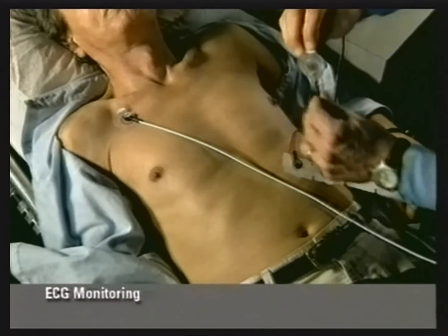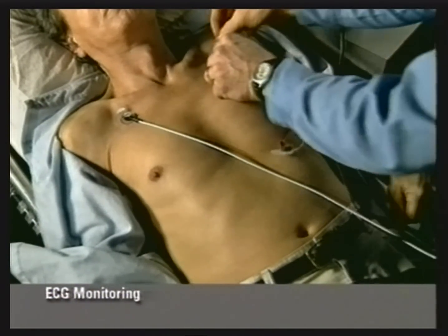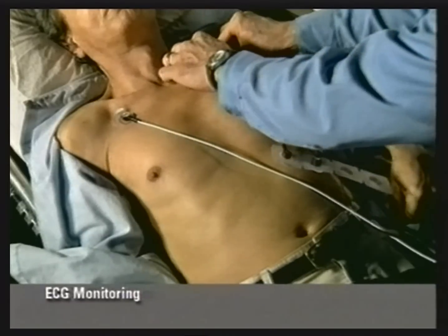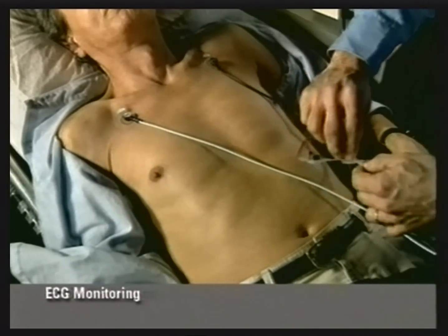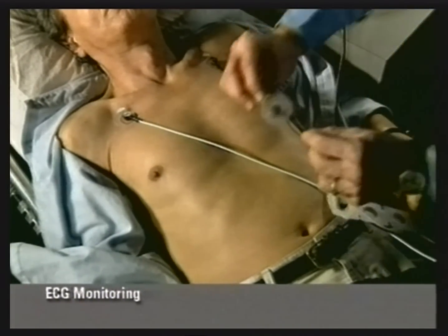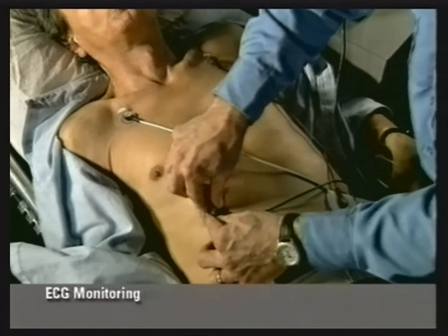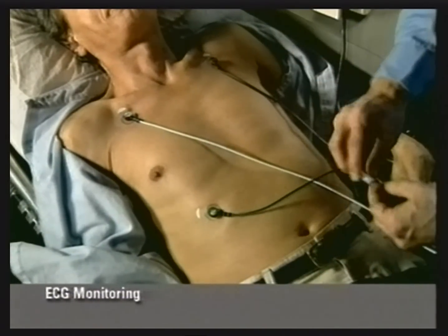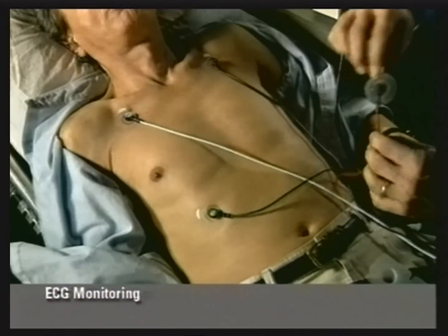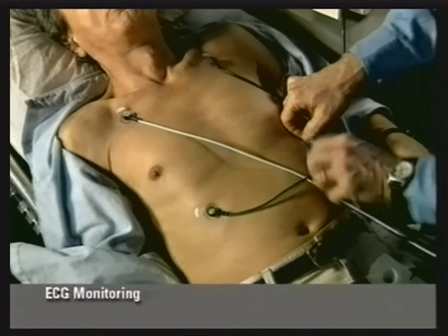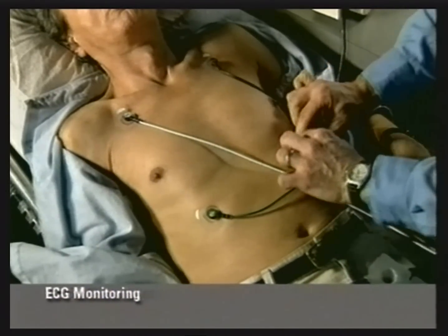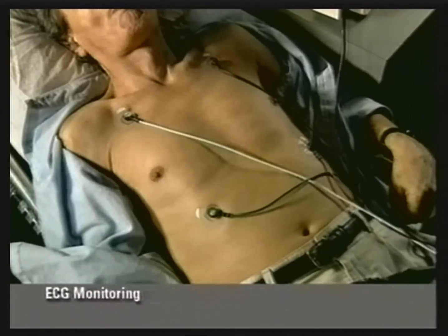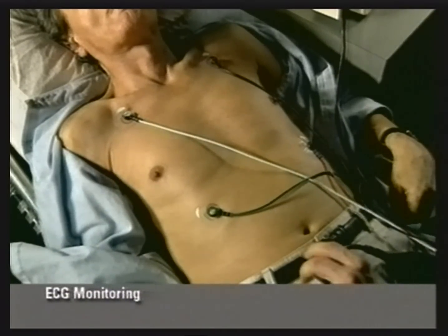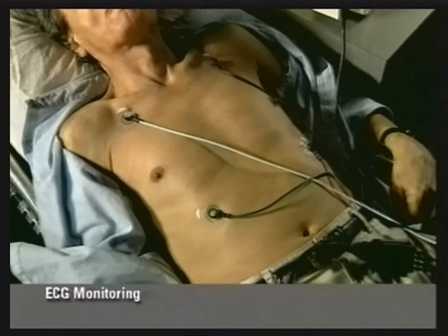Place the white right arm electrode on the patient's upper right chest below the clavicle. Place the black left arm electrode on the upper left chest below the clavicle. Place the green right leg electrode on the lower right chest, and place the red left leg electrode on the lower left chest. Secure the cable with the clasp to prevent tension on the electrodes.